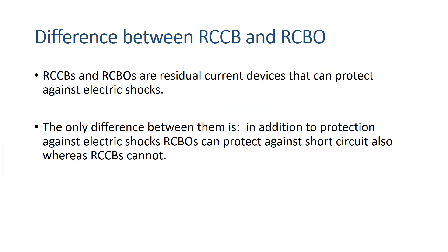Difference between RCCBs and RCBOs: RCCBs and RCBOs are residual current devices that can protect from electric shocks. The only difference between them is, in addition to protection against electric shocks, RCBOs can protect against short circuits also, whereas RCCBs cannot.